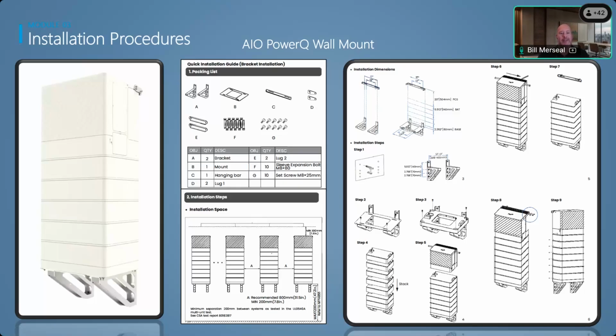If you've ever tried working on something that's only 8 inches apart, the doors are on the interior on the right-hand side, so you're going to have to find somebody very, very skinny to squeeze in there to work on those. If you have the room, I would recommend at least 12 inches apart, because that will give you room to put your screwdrivers and everything inside there. If not, it's going to be tight. It's possible, it works—that's why we said 200 millimeters apart, only if space only has that much room, guys.